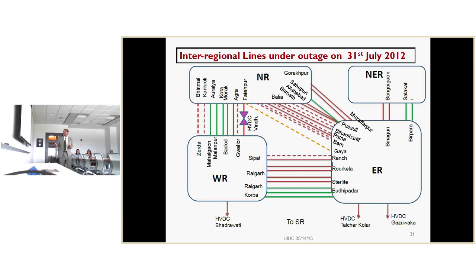That also tripped. The same thing happened on that day, although the real power flow was less, but reactive power flow was high on that day. So the same Bina Gwalior Agra line tripped on load encroachment, separating northern from western. But since this part was weak, the center of oscillation was somewhere here, which separated part of eastern along with western from northern, northeastern, and the major part of eastern region.